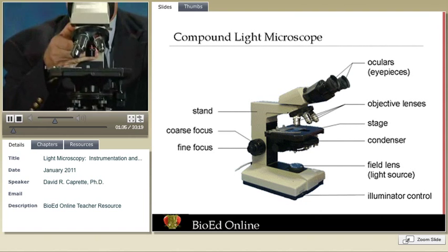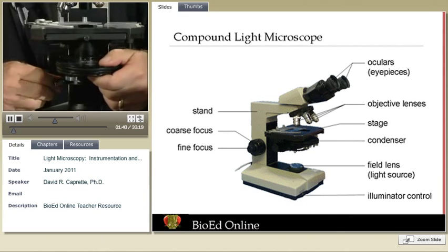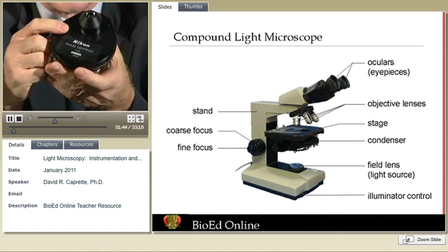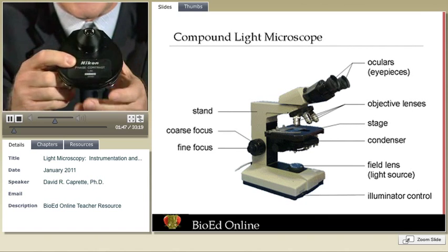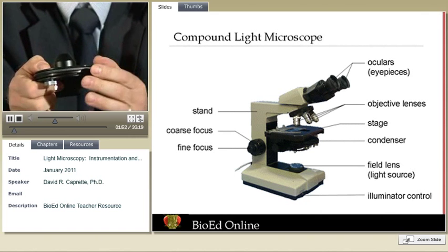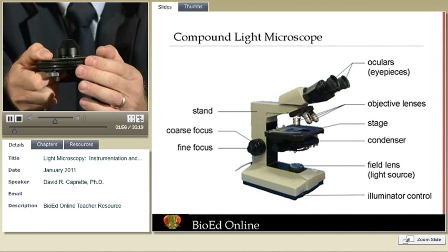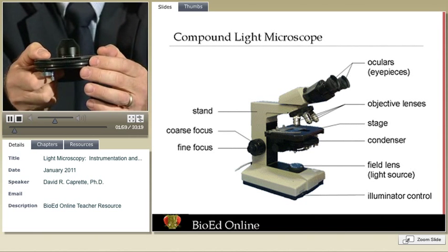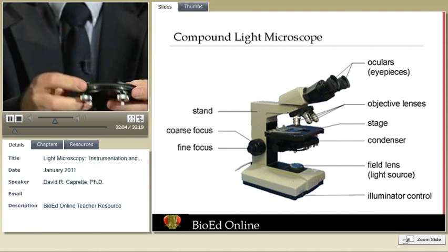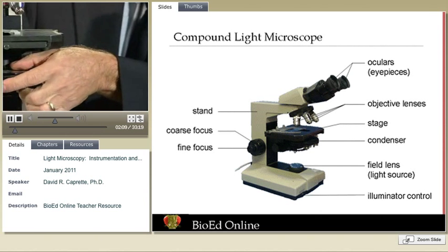A critical element in a compound microscope is called the condenser. The condenser has a lens that collects light from the illuminator, focuses it on the specimen, and usually has an apparatus for incorporating elements into the light path that give you specialized optics, allowing you to optimize the lighting for contrast and resolution. There's a neat little apparatus called an aperture diaphragm that we use to control contrast and resolution.